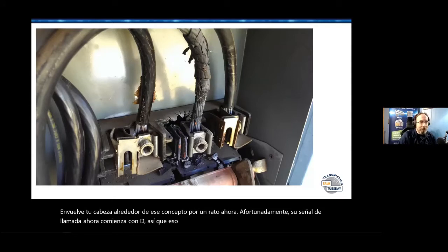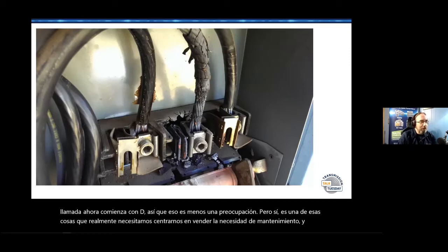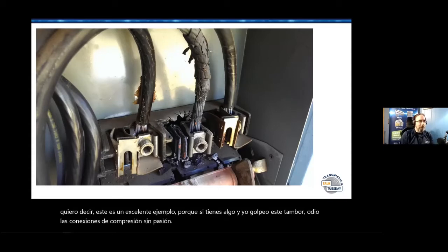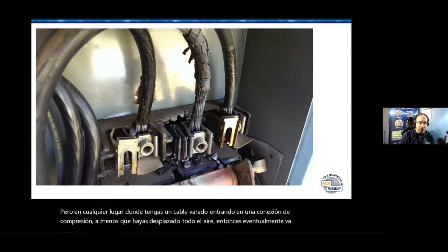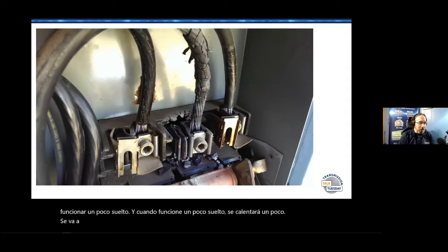It's one of those things we really need to focus on: selling the need for maintenance. This is a prime example, because I beat this drum—I hate compression connections with a passion. Anywhere you've got a stranded wire going into a compression connection, unless you've displaced all the air, it's eventually going to work a little loose. When it works loose, it gets a little hot, it oxidizes, which adds resistance, which makes it hotter, and it just cascades from there.